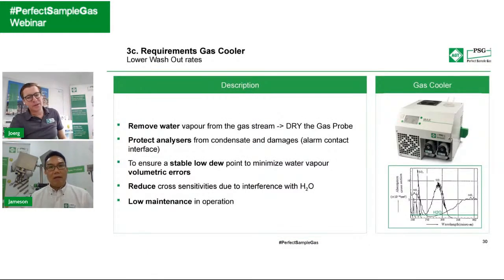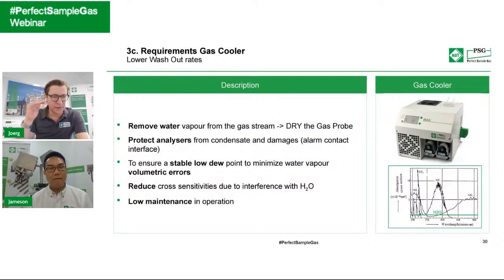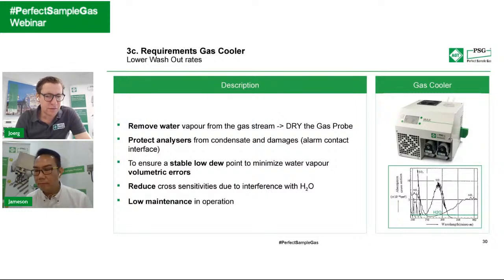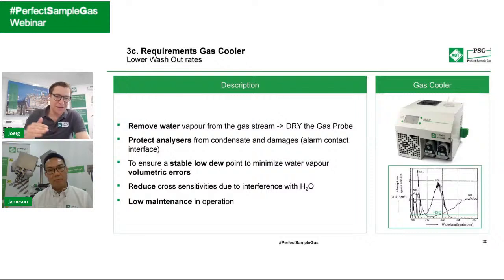And maybe also something else: you said, Jameson, that it is the task of the cooler to remove the water down to a certain, you said 3 degree outlet dew point. Some others operate at 4 or 5 degrees C outlet dew point. I think the importance is that the outlet dew point is constant, and therefore, as you already mentioned, it is also important to ensure that the flow inside your system is constant. Because always consider, if you make any changes to the flow and the pressure situation in this complex system, this will cause a change of the outlet dew point, which means a change of the remaining water in the probe, and this will also affect the accuracy and the reliability of the analyzer or of the analysis you are doing from the probe, right?